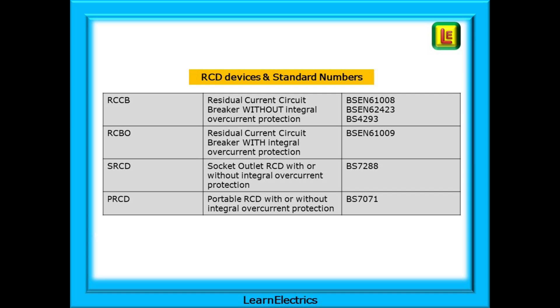RCBOs to BSEN 61009 will detect residual currents and overloads of current. They have an I-delta-N — a residual tripping current rating — and an overload current rating. So an RCBO can perform the functions of both an RCD and a circuit breaker. We also have standard numbers for socket outlet RCDs and portable versions that can be moved about and plugged in where needed.